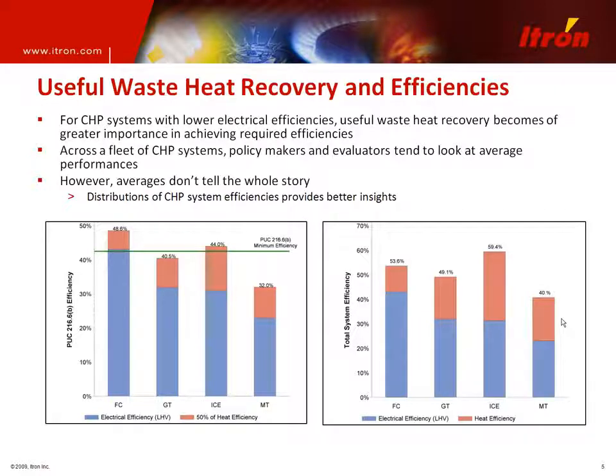One of the things that we've noticed is that when you start talking about a fleet of CHP systems, people tend to look at average performances. But if you're really looking at an average performance, you don't get the whole story. And so if you notice here, the slide on the right is really this 216.6B efficiency, which is the combination of the thermal and electrical. And you can see that gas turbines in this particular instance had a problem achieving that 42.5% efficiency as well as microturbines.